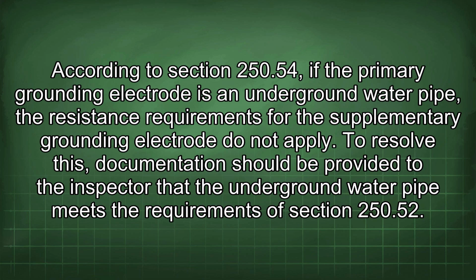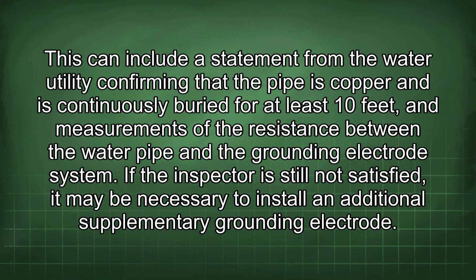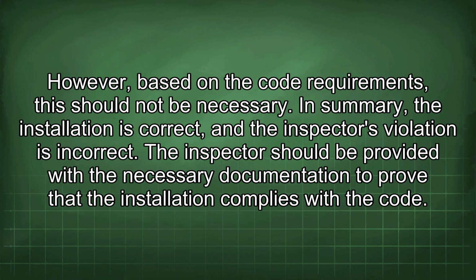To resolve this, documentation should be provided to the inspector that the underground water pipe meets the requirements of Section 250.52. This can include a statement from the water utility confirming that the pipe is copper and is continuously buried for at least 10 feet, and measurements of the resistance between the water pipe and the grounding electrode system. If the inspector is still not satisfied, it may be necessary to install an additional supplementary grounding electrode. However, based on the code requirements, this should not be necessary.